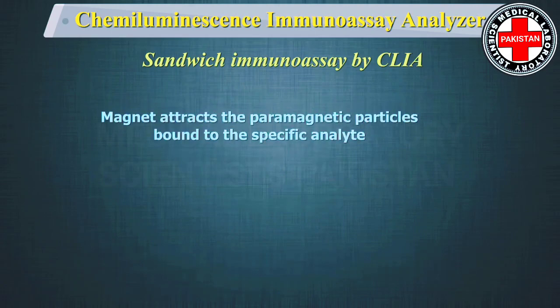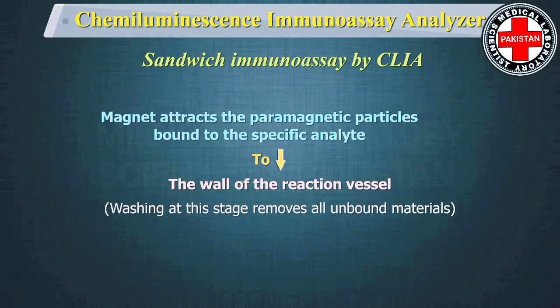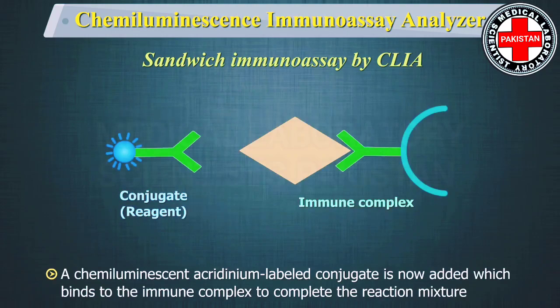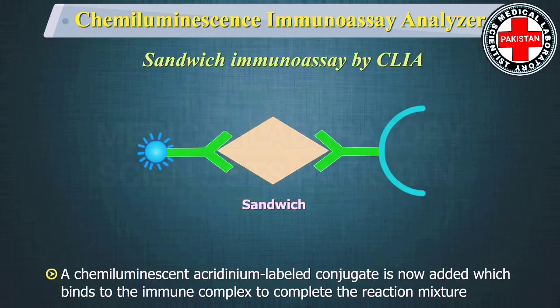A magnet attracts the paramagnetic microparticles, now bound to the specific analyte, to the wall of the reaction vessel. Washing at this stage removes all unbound materials. A chemiluminescent acridinium-labelled conjugate is then added, which binds to the immune complex to complete the reaction mixture.